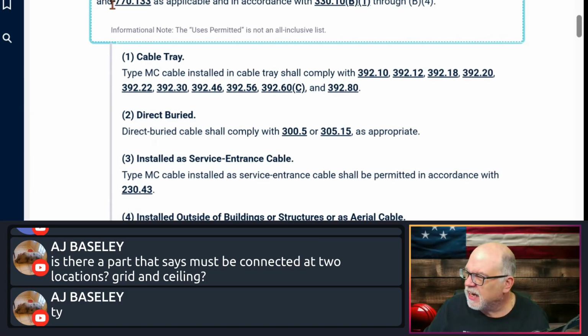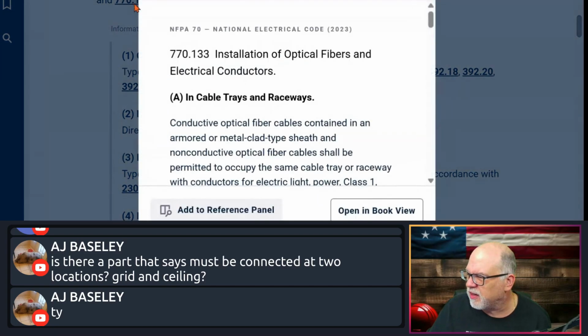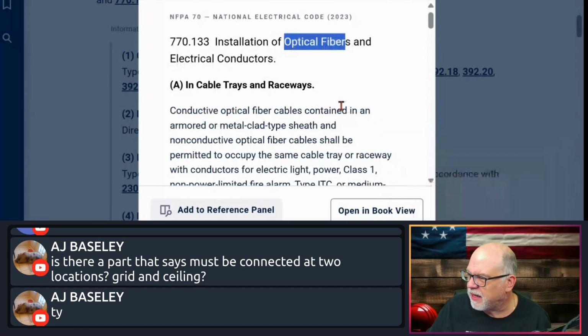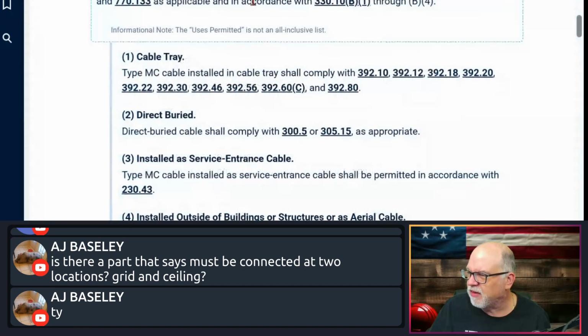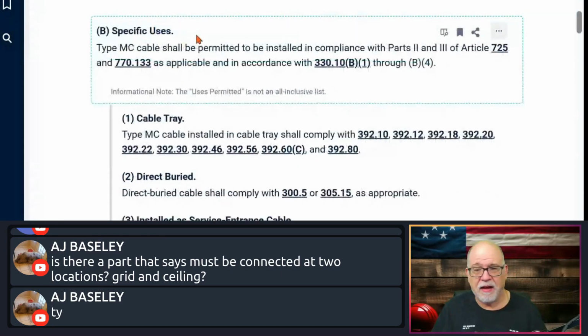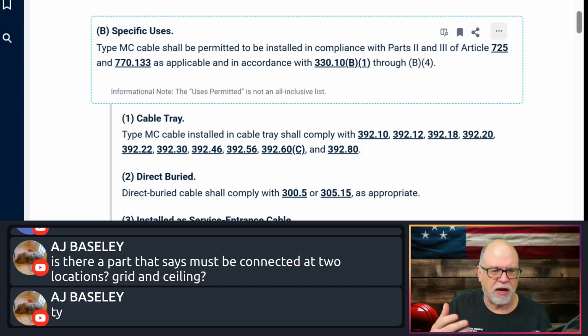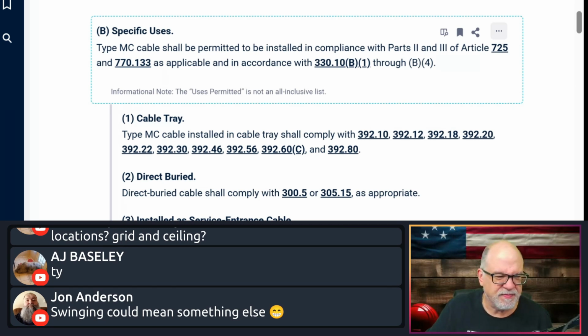So that follows that. And then 770, you have probably seen applications where we have something like fiber optics inside of MC. Let me click on that so you can see it. This is optical fiber applications. So you have allowances specific for that, where you can have an MC cable that has power conductors in it, but it will also have 0 to 10 volt or lower voltage type conductors run with it, or it will have fiber optic cables run with it. Again, you can get a bunch of different flavors of MC cable depending on your application. But you and I are probably used to the everyday workhorse, just regular old MC cable. You know what I'm saying?